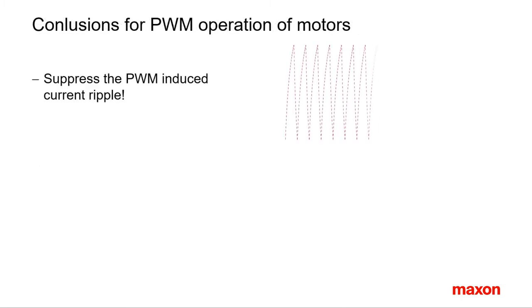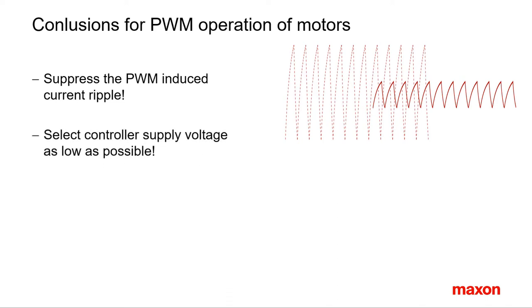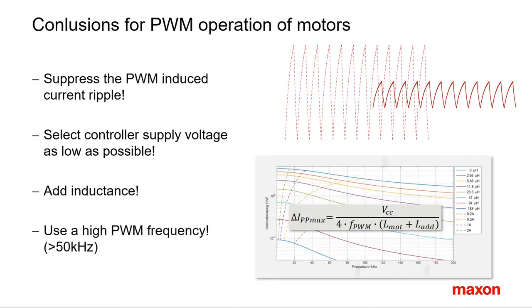A summary. Reduce the current ripple as much as you can. Select a low supply voltage in order to maximize the PWM duty cycle. Add extra inductance and use PWM frequencies of 50 kHz and above. Maxon controllers follow these rules as well. They have a high switching frequency and a built-in motor chokes to be well adapted to the low inductance Maxon windings.